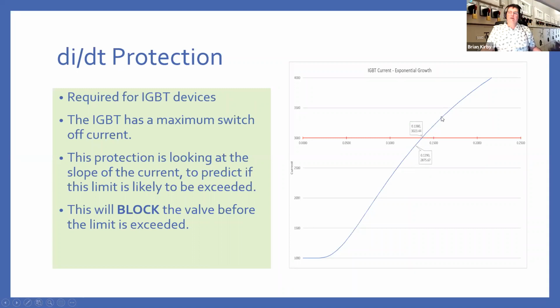rapidly rising current profile. If we switch off at this point here, after 129 milliseconds, we're less than 3000 amps, so we can switch off the IGBT and we can block the valve at that point. If we just wait another 9 milliseconds, we've exceeded the 3000 amps and we no longer can isolate and block with the IGBT, and then we're into the realm of having to shut down the AC side. So this is a bespoke function for VSC systems.